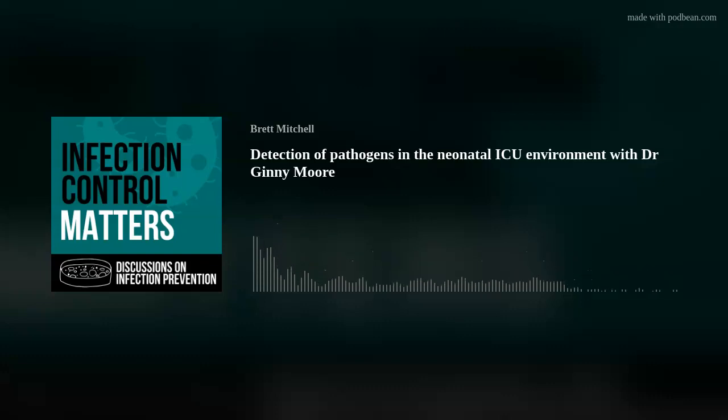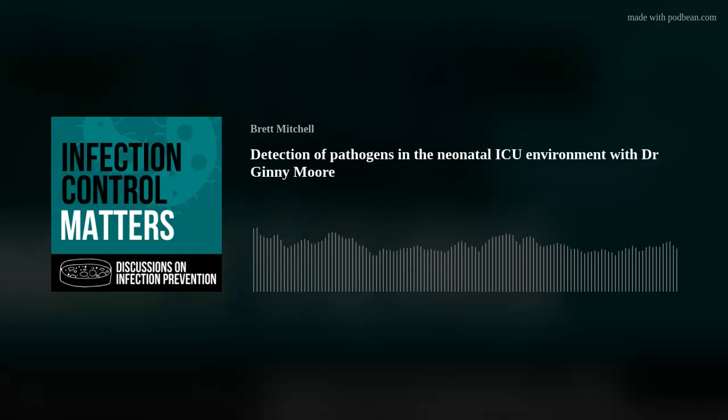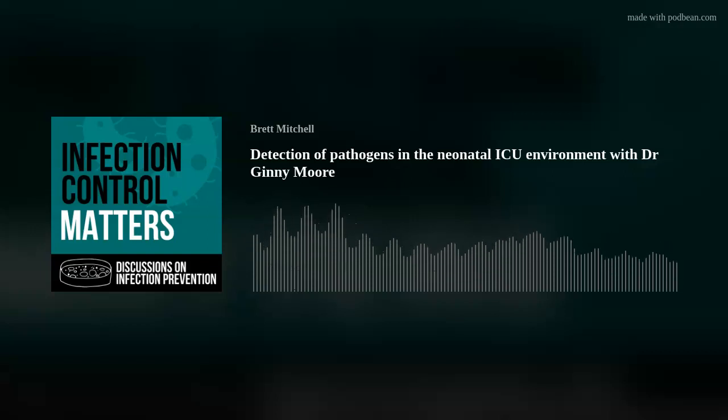So certainly it was interesting talking to some of the staff as to the difficulties that they found with some cleaning products. Some did bring up the fact that some cleaning chemicals can damage the plastic covers, which makes it difficult for them to see through as well. That's about the practicalities of using the thing, not just cleaning it. We didn't notice that, but that wasn't the focus of the investigation. Anecdotally, though, some of the cleaning chemicals were highlighted as having a bit of material incompatibility going on.